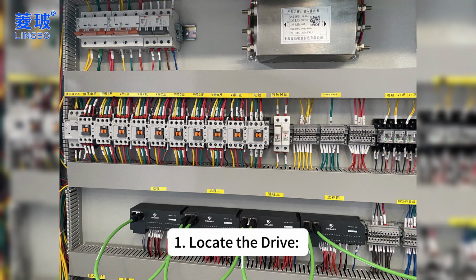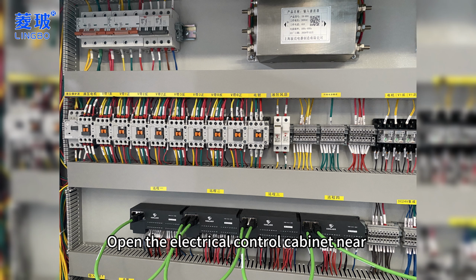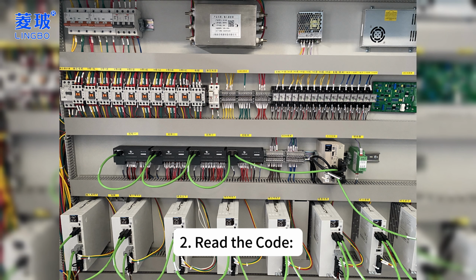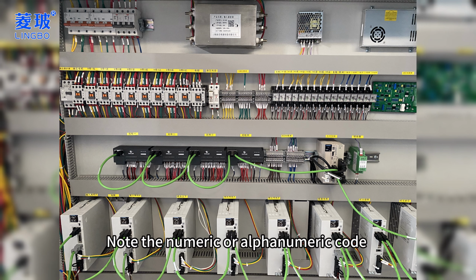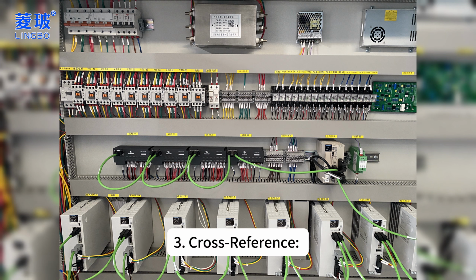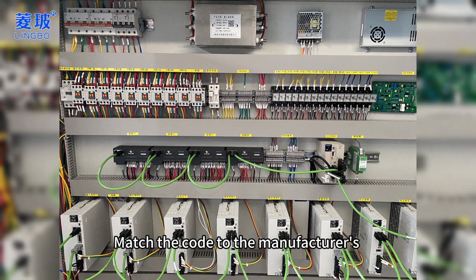Step 1. Locate the drive. Open the electrical control cabinet near the conveyor section. Step 2. Read the code. Note the numeric or alphanumeric code displayed on the drive's LED panel. Step 3. Cross-reference. Match the code to the manufacturer's manual for specific causes.